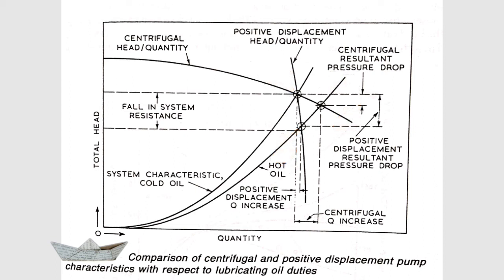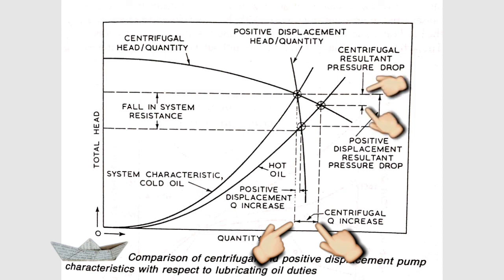Another big advantage is that the centrifugal pump used as a lube oil pump is always located inside the main engine lube oil sump. The pump sits at the bottom, so the lube oil always provides a positive suction head to the pump — that is a big advantage. We only need to maintain a minimum level of lube oil inside the sump. Overall, the centrifugal pump is more efficient, delivers higher flow rate to lubricate engine parts, and has less pressure drop compared to the positive displacement pump.